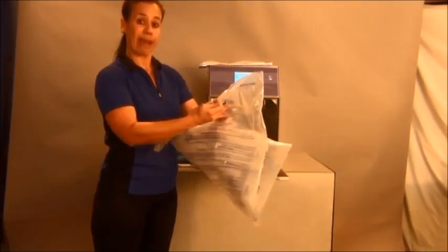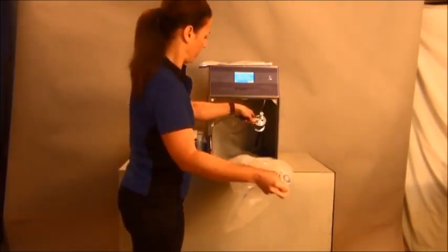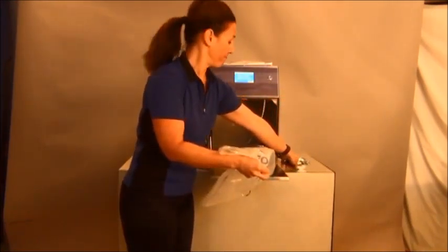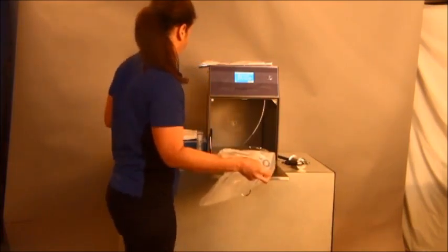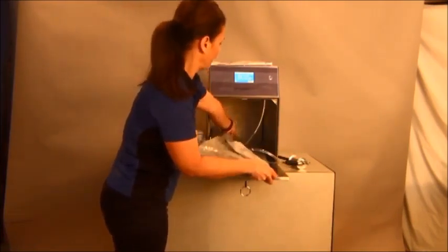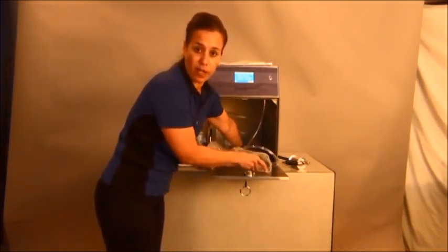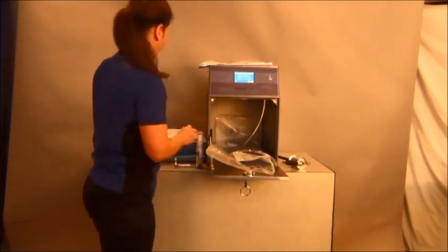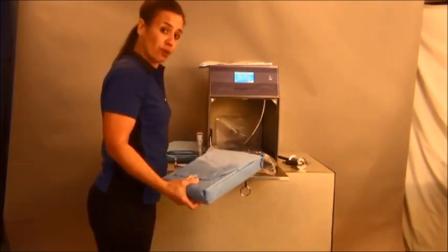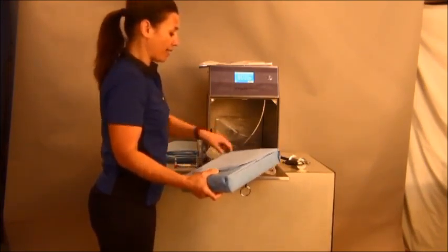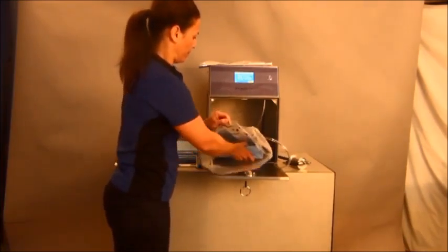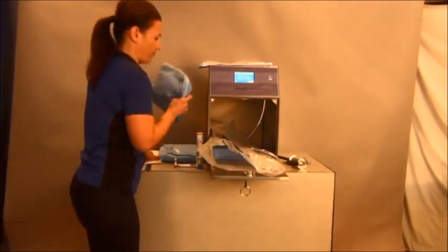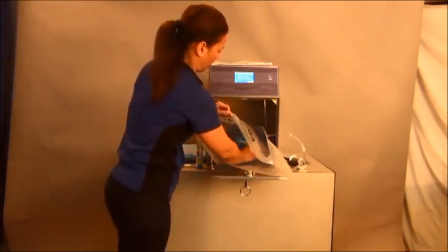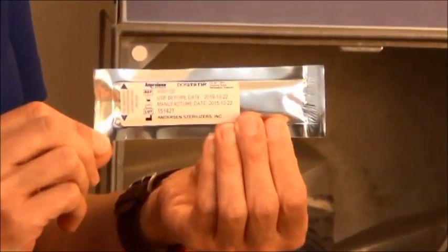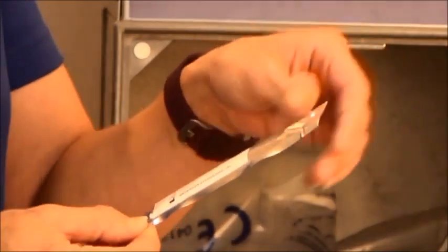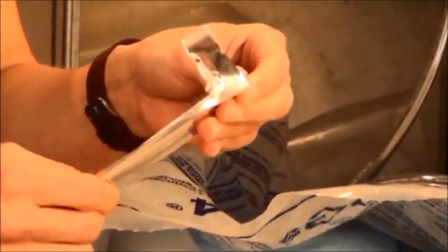I'm going to place my sterilization liner bag into the system and put my purge probe to the side. If you need to bend your liner bag to get it in, depending on what items you're sterilizing, that's absolutely fine. Again, in a uniform and comfortable fashion, you want to place your items into your liner bag. At this point, I'm going to put my dosimeter, which is my chemical indicator, into the least accessible portion of the liner bag.